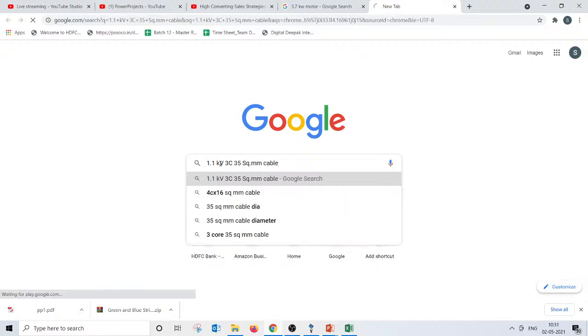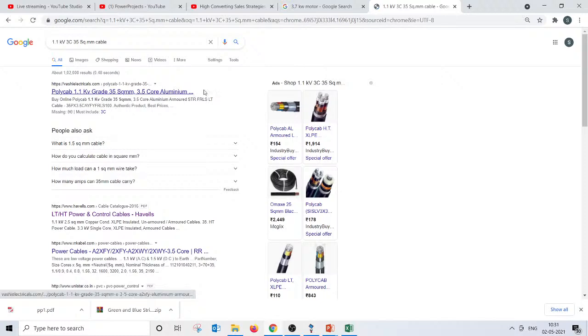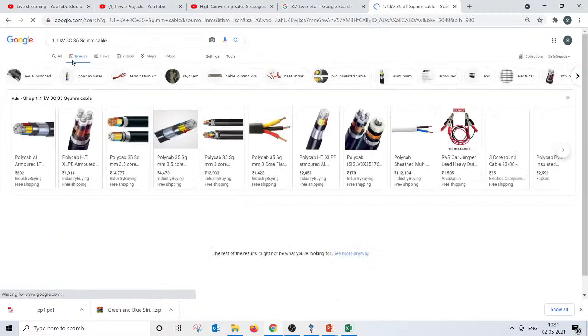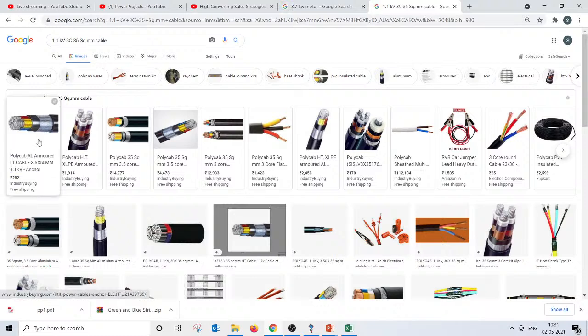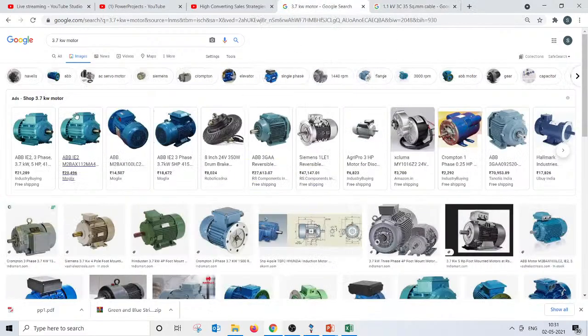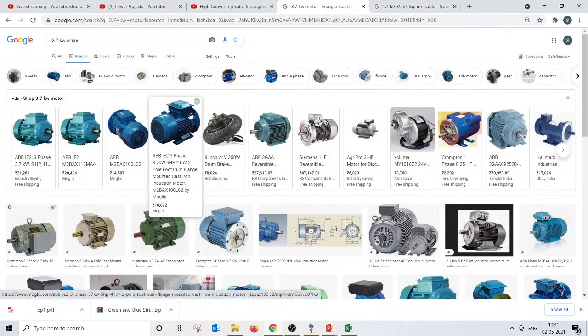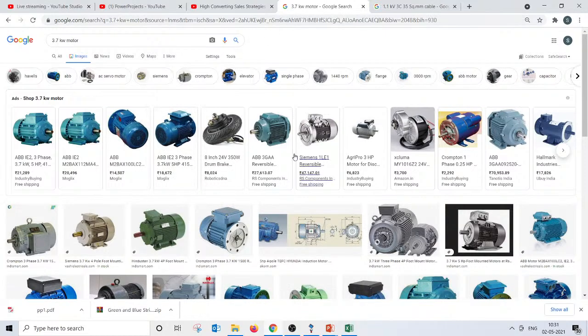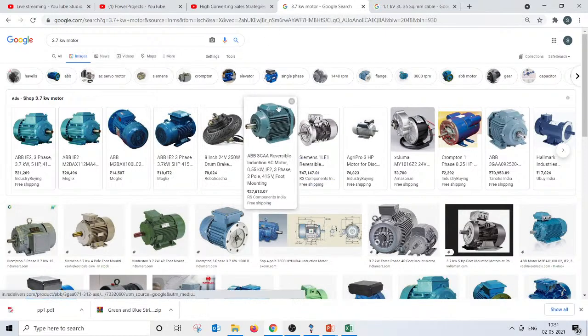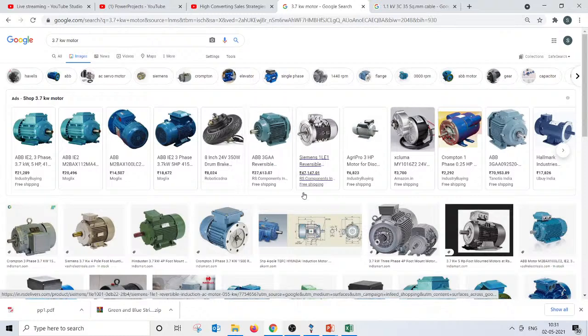Like, try to find some images, right? Anyway, we may not be able to get exactly for a 35 square cable because we really do not know what the size of this is. But you can imagine, if it is a 35 square cable, putting that into the motor cable terminal box is not that easy. So generally you may go with maybe a 4 square cable or even a 2.5 square cable, which might be more than sufficient to carry that current, even considering the voltage drop.